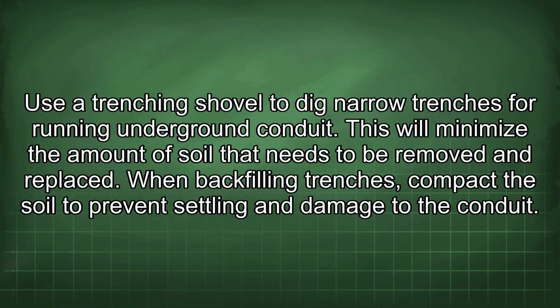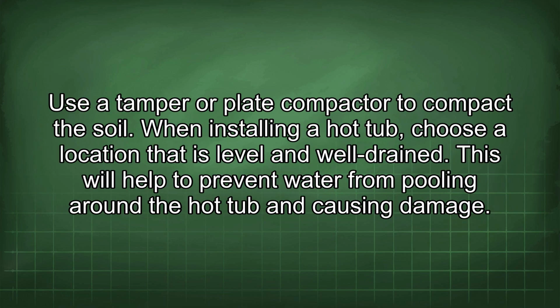Use a trenching shovel to dig narrow trenches for running underground conduit. This will minimize the amount of soil that needs to be removed and replaced. When backfilling trenches, compact the soil to prevent settling and damage to the conduit. Use a tamper or plate compactor to compact the soil.